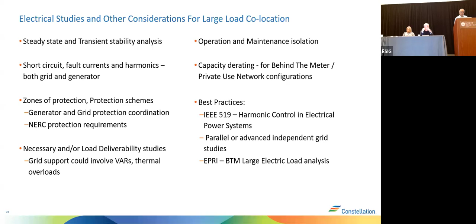Good morning, everyone. Over the past two days I've heard the term co-located, and I want to clarify from my perspective, and I guess the ERCOT perspective, co-location does not necessarily mean with existing generation. For us, it's the same thing: once we get an interconnection request, if they have backup generation that could be synchronized to the grid, we treat it the same way as if you're interconnecting with existing generation. We have to go through all the studies. So when I'm talking about what we're doing in ERCOT, think of it in that term—it's not necessarily with existing generation, it's with backup generation that could be synchronized to the grid.